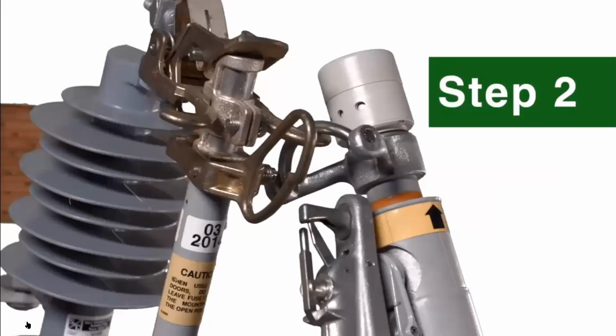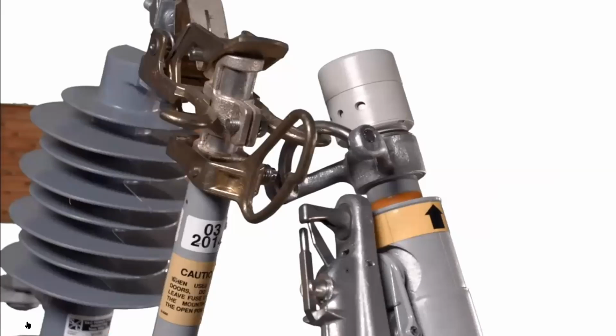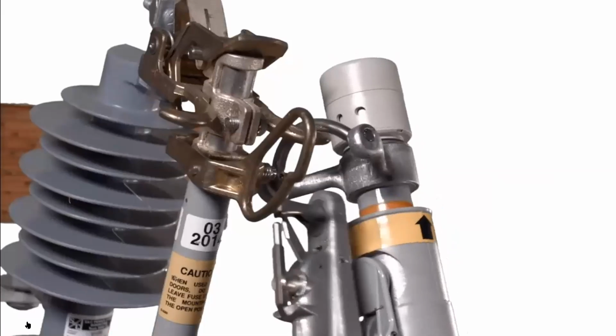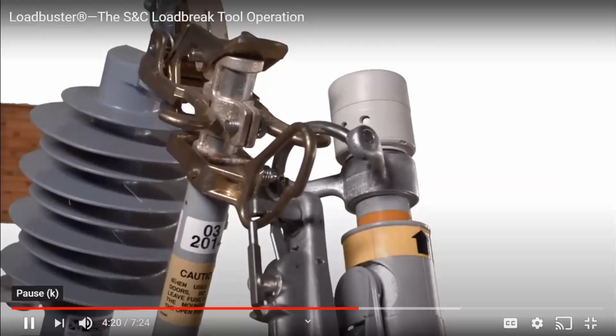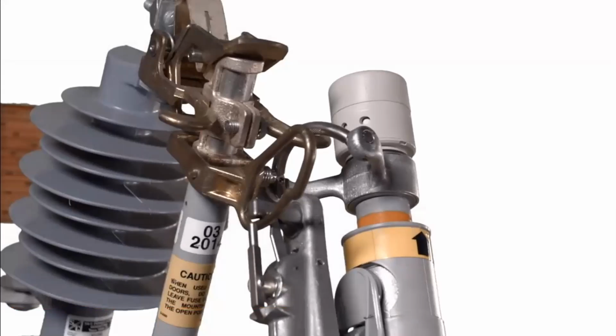Step 2. Swing the load buster tool toward the SMU20 fuse itself and pass the load buster tool pull ring hook through the pull ring on the fuse. The pull ring latch will deflect and, upon complete entry of the pull ring, will spring back, locking the load buster tool to the pull ring.